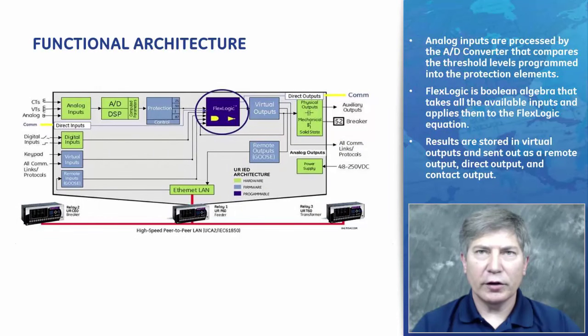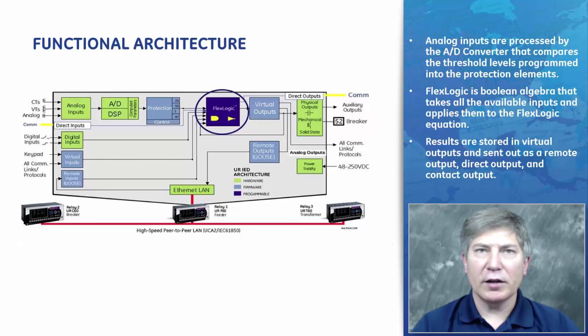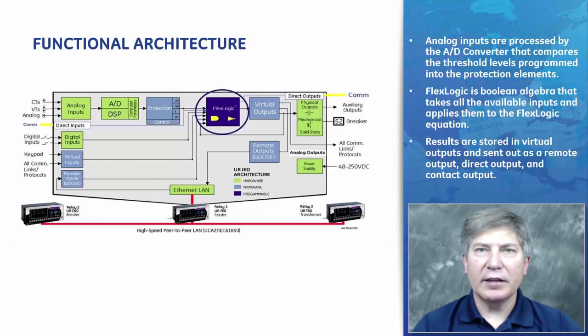The functional architecture of the UR relay has all inputs on the left and all outputs on the right. Inputs from CTs, VTs, and analog inputs are put through an A-to-D converter to compare against thresholds programmed into the protection elements. The results from protection elements, along with digital inputs, virtual inputs, and remote inputs, are used in the flex logic block. Flex logic is the Boolean algebra that takes all available inputs and applies them to flex logic equations. The results are stored into the virtual output, which can then operate a contact output to open a breaker, send a GOOSE message via remote output, or send a direct output to another UR.